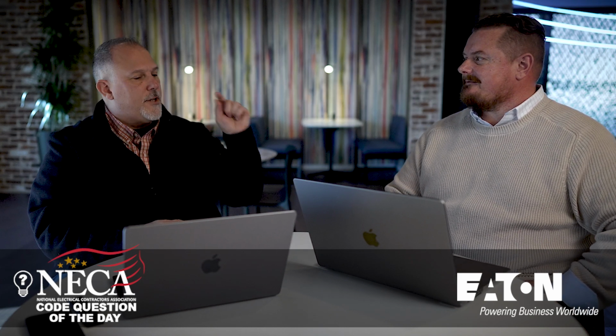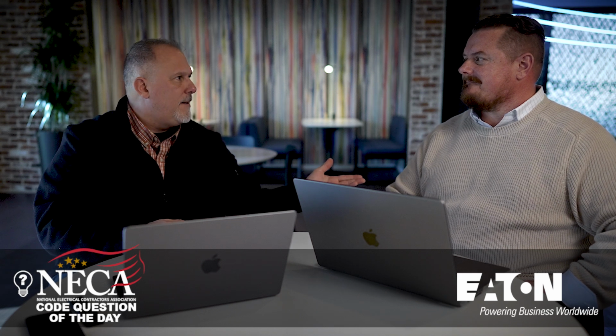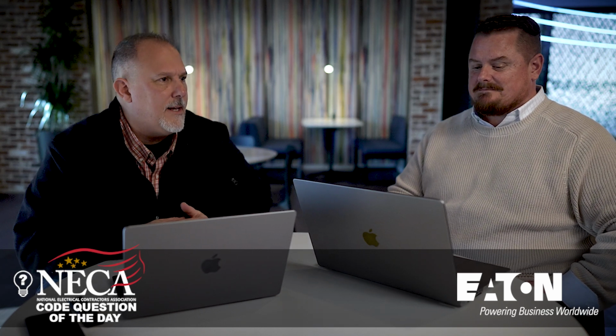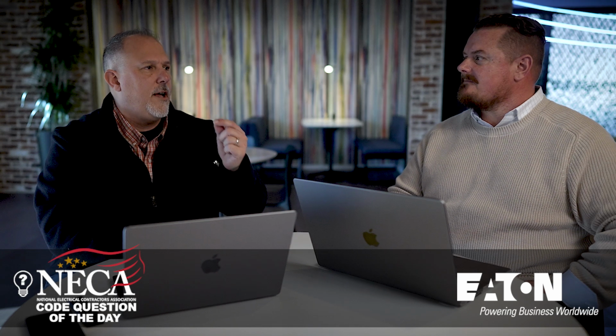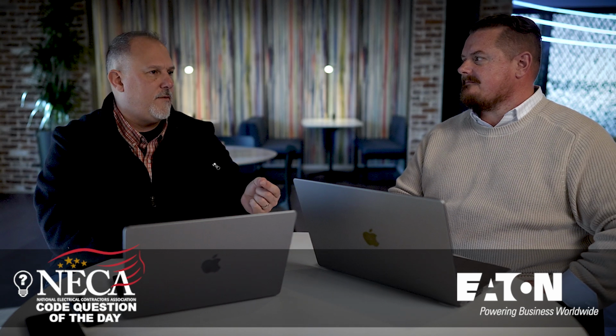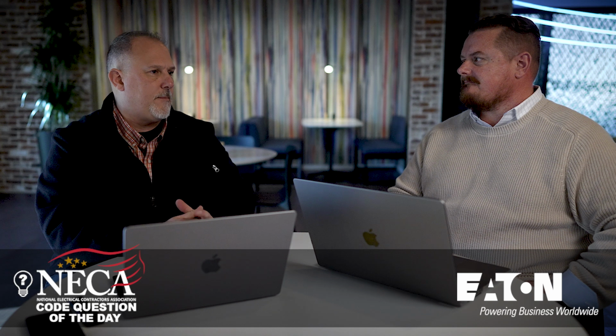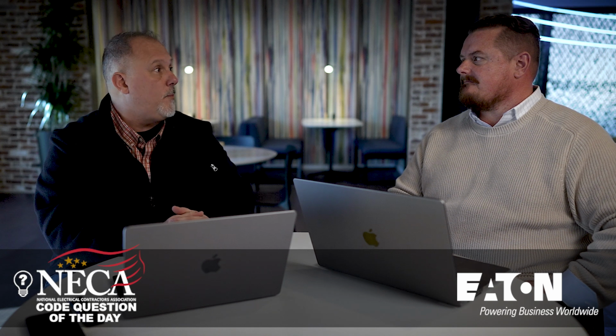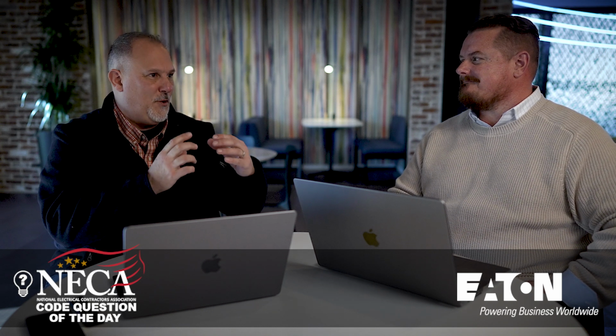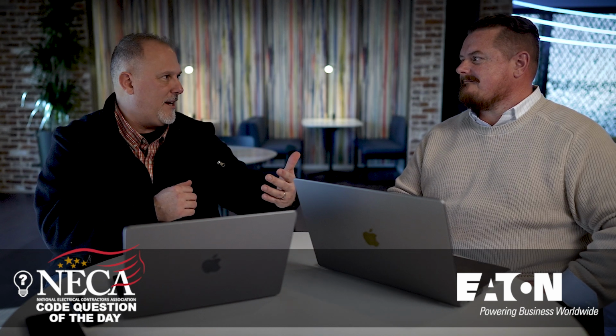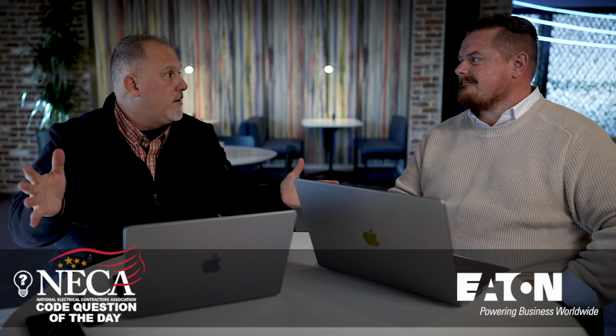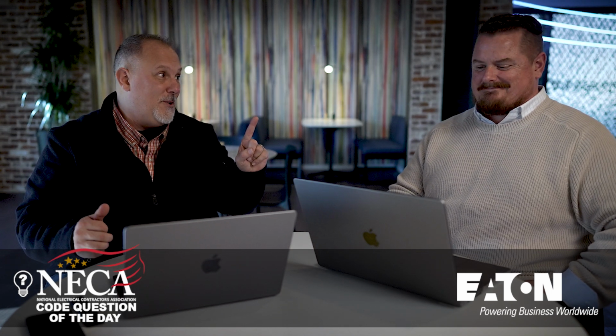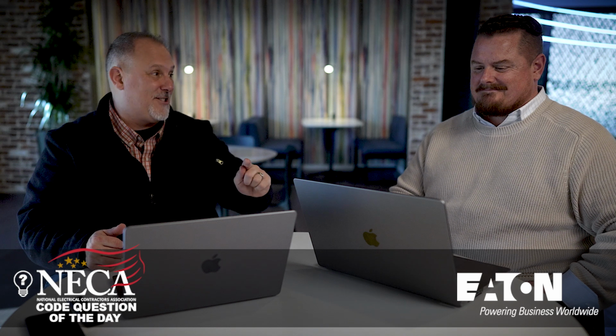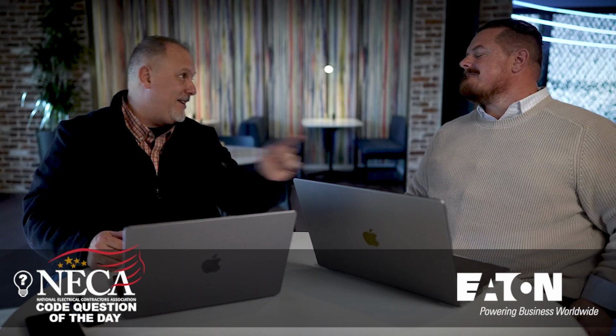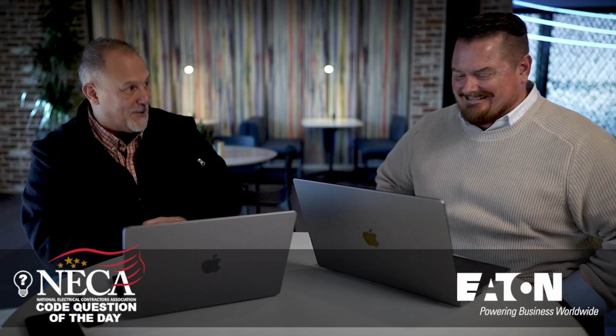thing. You can install it, voltage same way. Yeah. I've had people ask me, they say, can I install a 120 volt circuit breaker on a 240 volt application? I'm like, well, you can, but just don't let it open, right? So if you put a 5,000 amp interrupting rating or a 10K interrupting rating overcurrent device in that place, it will supply power. But the first opportunity that you actually have a call to action to do something, that's when the unintended rapid disassembly in the field is going to occur.